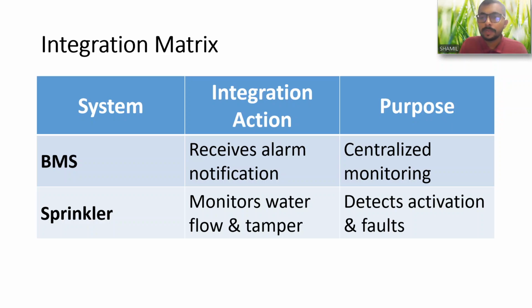In the sprinkler system, if there is a water flow movement, or if someone has unnecessarily turned off or closed the valve in any location, these actions, the water flow movement and the tampering of the valves, will be signalled and communicated to the fire alarm control panel. The fire alarm control panel will then detect this and notify the building occupants or the first emergency responders. Okay, so this is how the sprinkler system communicates with the fire alarm system.